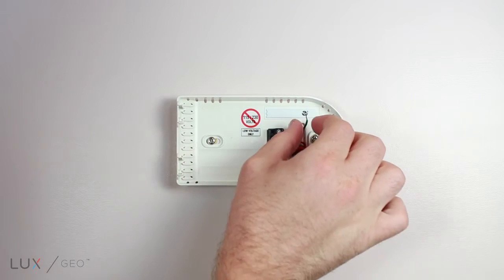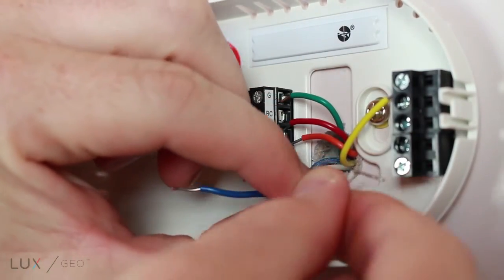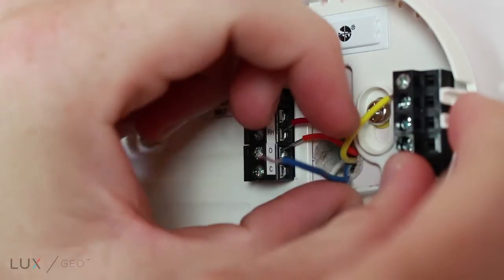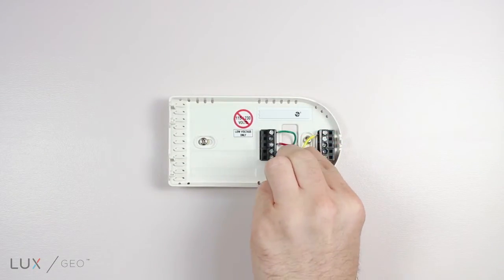The blower fan is green and will be connected to the G terminal. Auxiliary heat is white and will be connected to the W2 terminal. The 24 volt common is blue and will be connected to the C terminal.